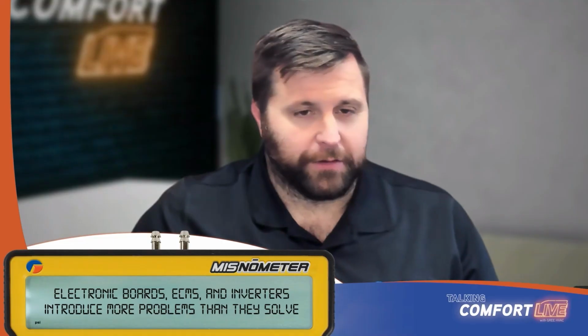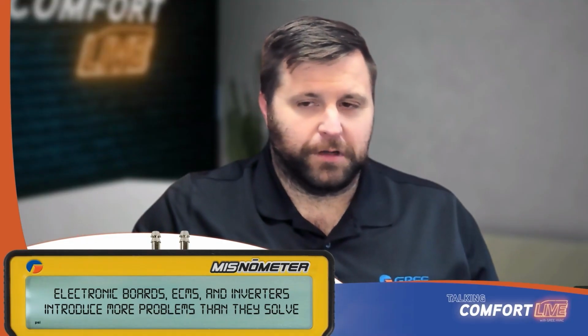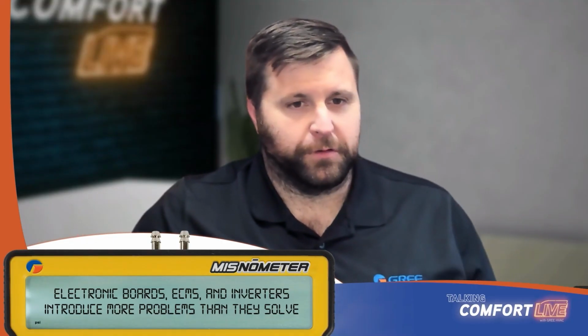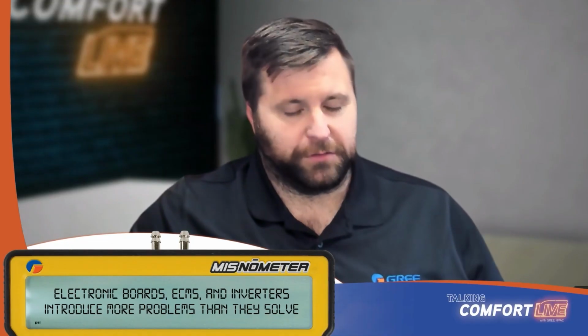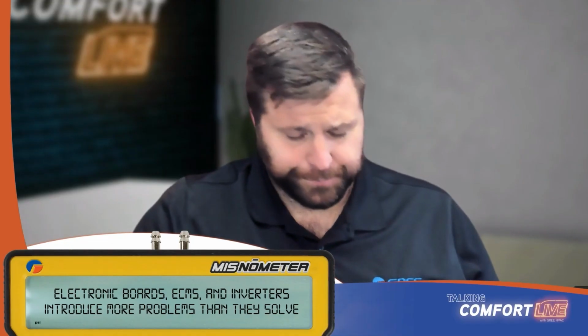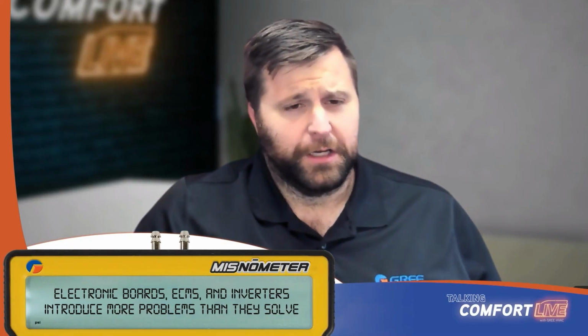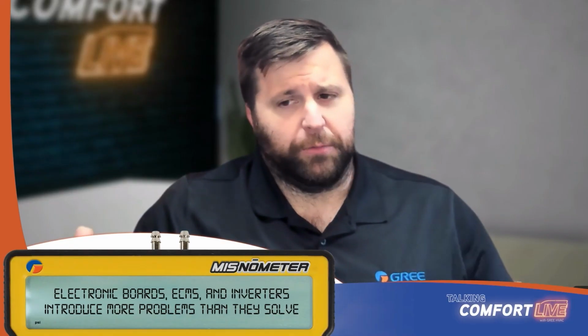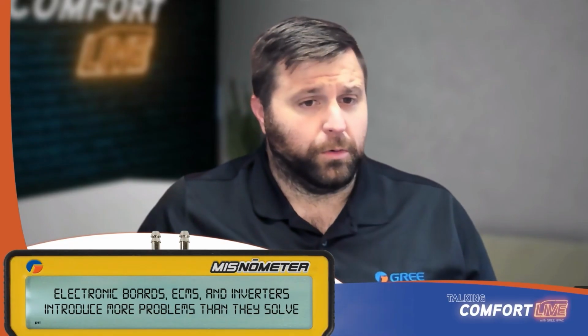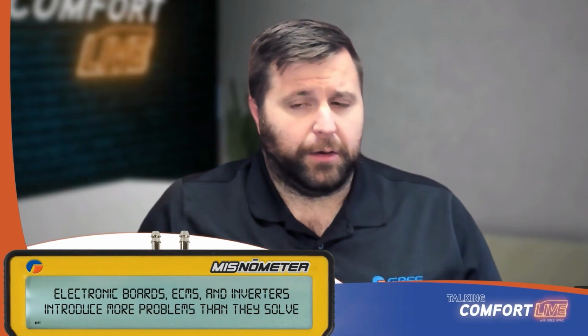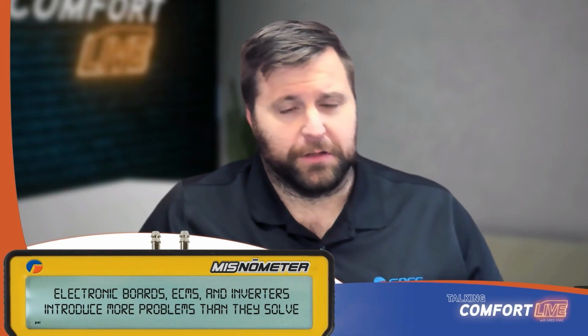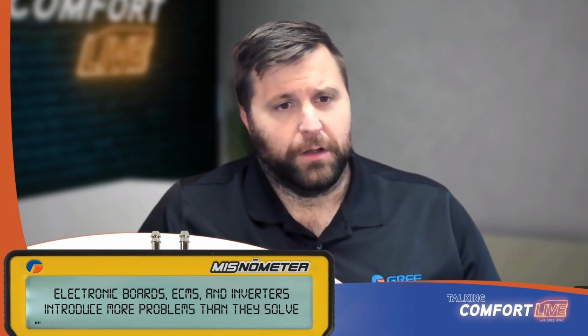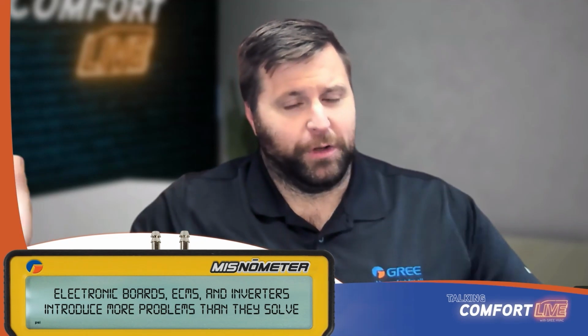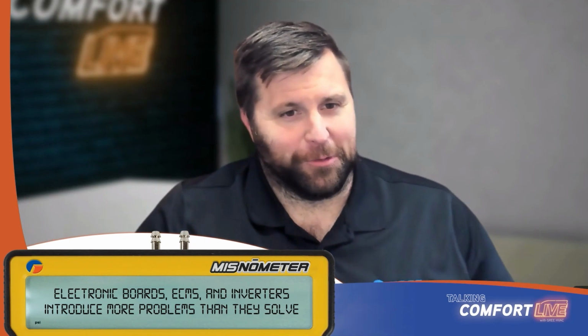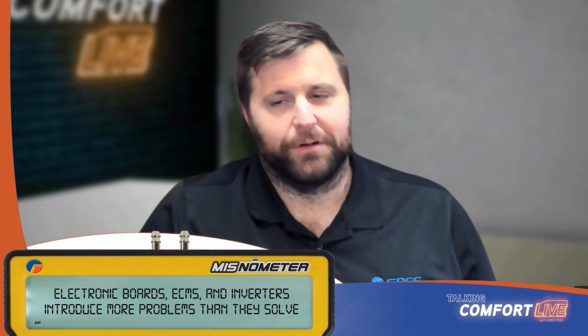At least reduced life. So although there are differences, you've got the inverter boards, you've got the electronic stuff, all that stuff. So much is built in from a protection standpoint that it'll help it to last a lot longer and continue to cool. On top of that, I like the fact that it gives me at least a direction to go in with an error code, rather than hooking up a whole bunch of stuff to find out what might be wrong.